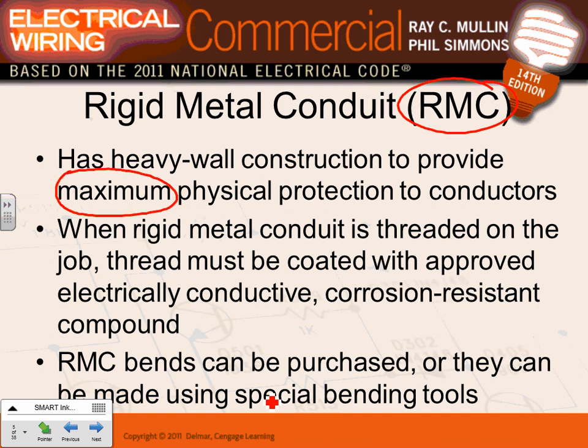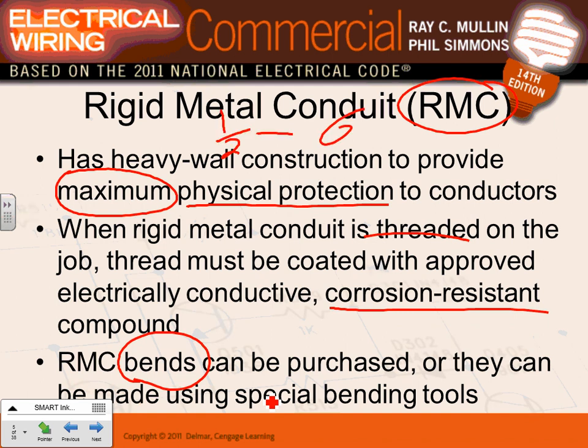It's thick, threaded, and if you thread them in the field you have to apply corrosion-resistance compound to protect them. You can bend these in the field or buy pre-bent. They come in sizes from half an inch all the way up to six inches. Steel comes to six inches.